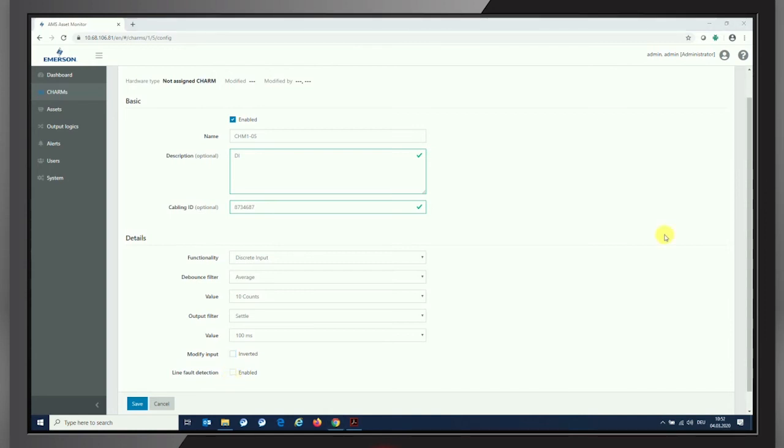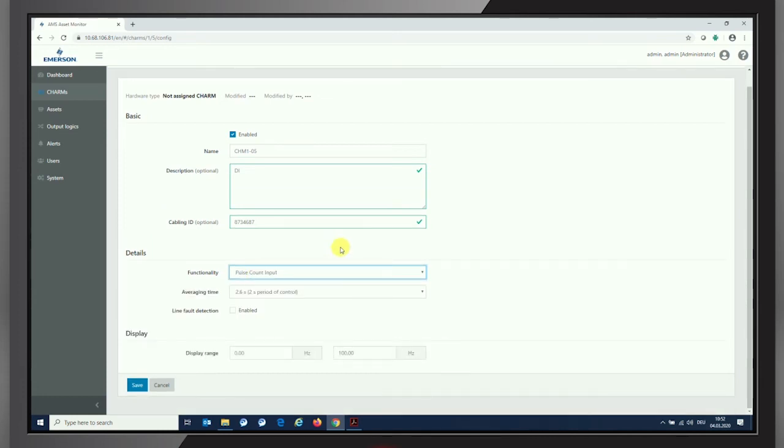But as said earlier, there is a second functionality the digital input charm can be used for, and this is, if we're moving back to the functionality section here, it can also be used to count pulses at the input. So it's just counting the pulses and measuring the amount of pulses over a period of time for detecting the speed of the machine. So we're using the digital input charm as well for getting a speed information into our calculations. It's not a key information, don't misunderstand that. It's just counting the pulses and measuring the time.